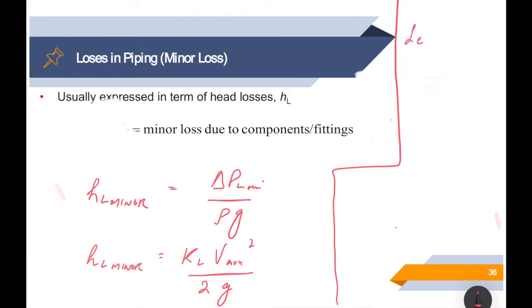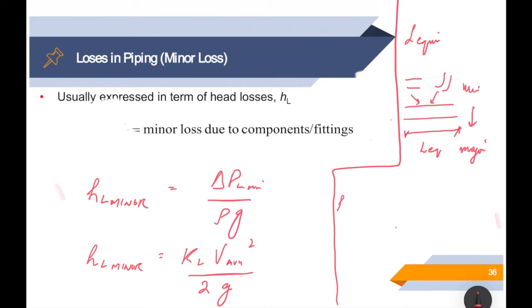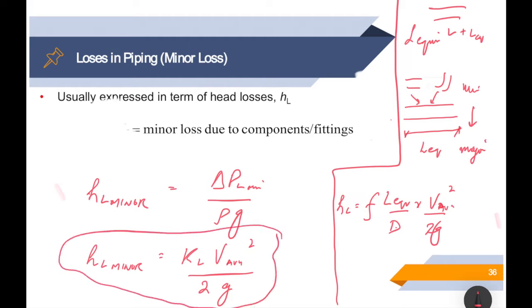There is an additional method — not included in this course — called the equivalent length method. In this approach, fittings such as elbows are converted into an equivalent pipe length L-equivalent, and their losses are expressed as major losses. The formula is HL equals f times L-equivalent divided by d, times V-squared over 2g. Some manufacturers and mechanical engineering services use this method, but we will use the KL expression in our course.